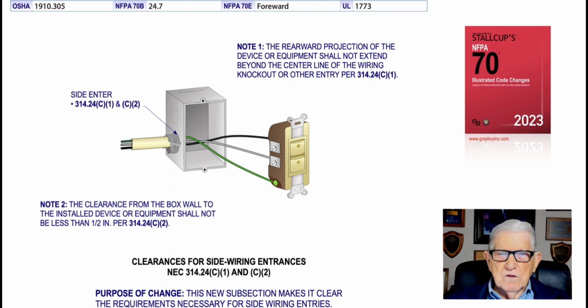Now this illustration deals with clearances for side wiring entrance. The purpose of this change is just a new subsection to clarify that there is a clearance needed from the side of that switch where the conductors enter. And what is that clearance? Well, note 2 tells you it's a 1/2 inch, and that's when the wiring is entering from the side. They want at least a 1/2 inch clearance there when you mount that switch, so that you have space that will not damage insulation of the conductors, and then still have a circulation air gap. And that's what this illustration is illustrating to the user of the NEC.